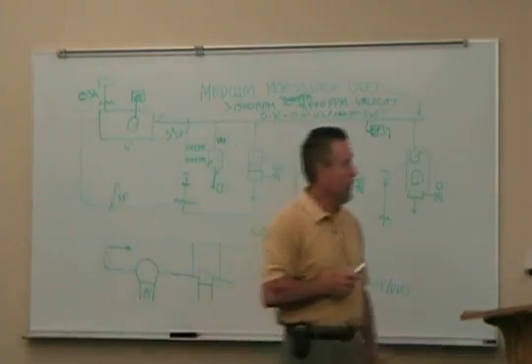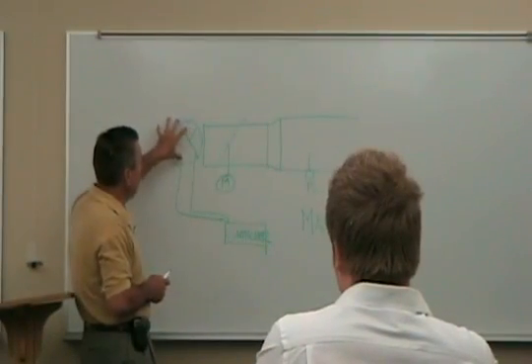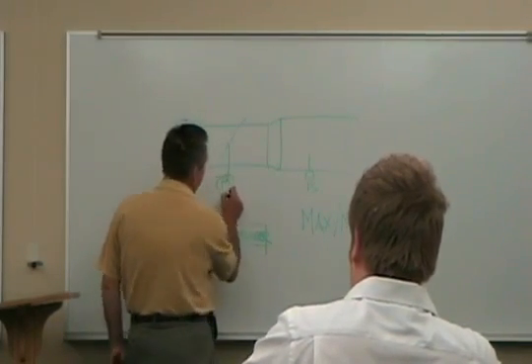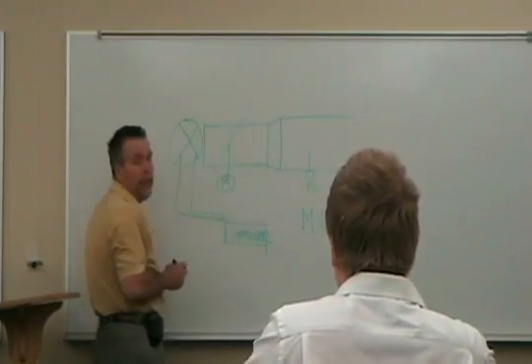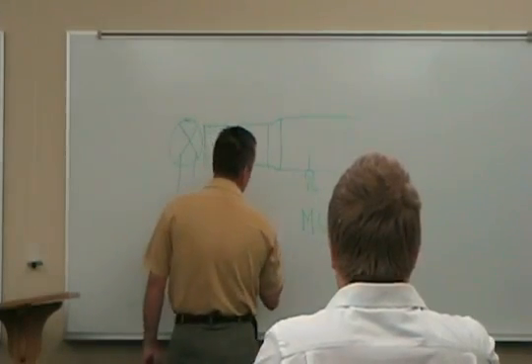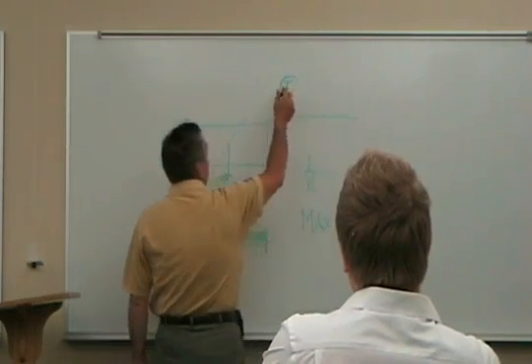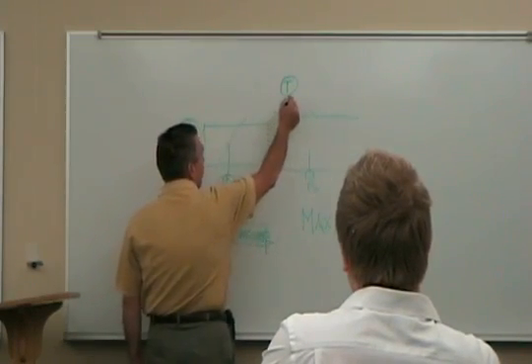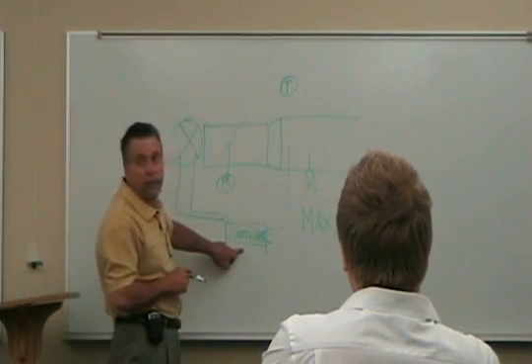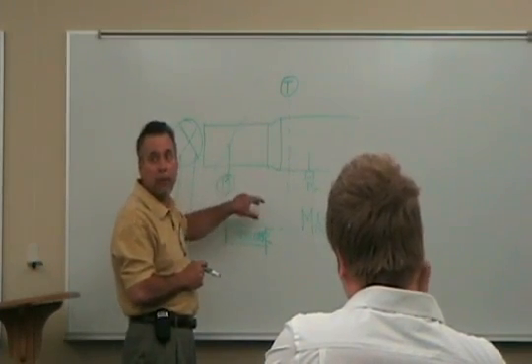So that's why this controller is measuring the airflow, measuring the velocity, calculating the area, or knows the diameter, calculates the airflow, and it's modulating this motor, opening and closing that damper to maintain the maximum and minimum airflows. The thermostat in the space is doing the same thing. It's telling that damper, it's talking back to this controller, and it's saying, I need airflow. So it's going to open that damper up to its maximum set point.